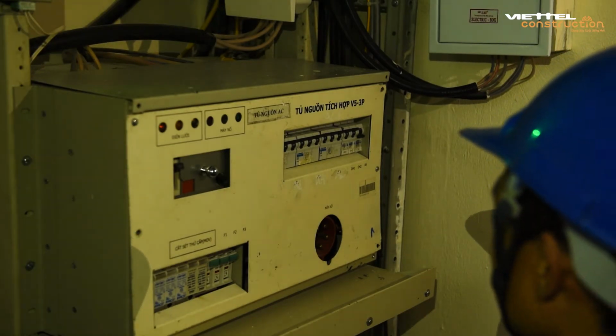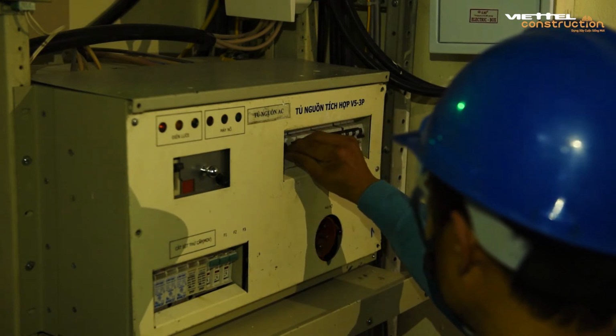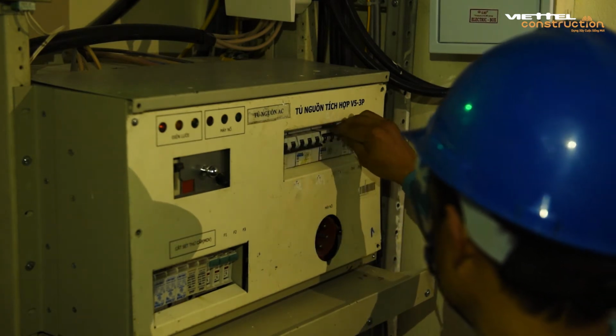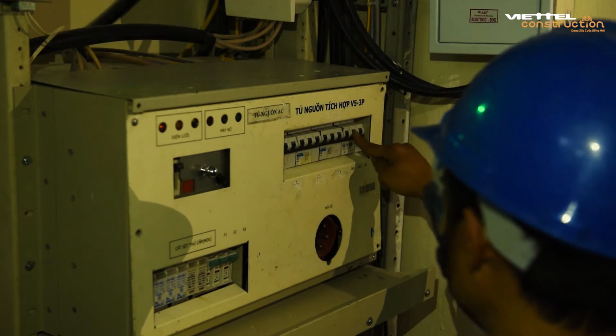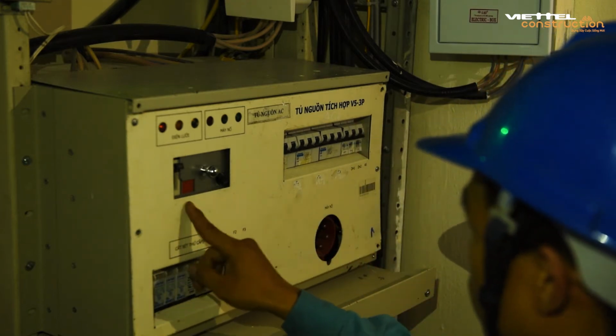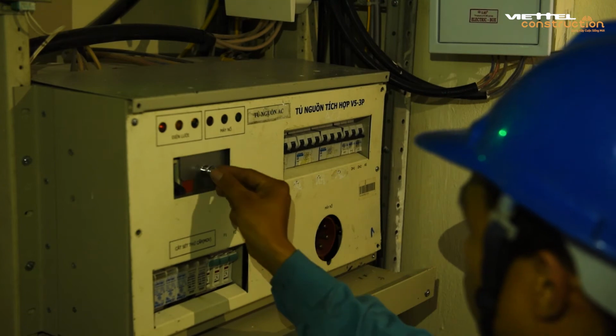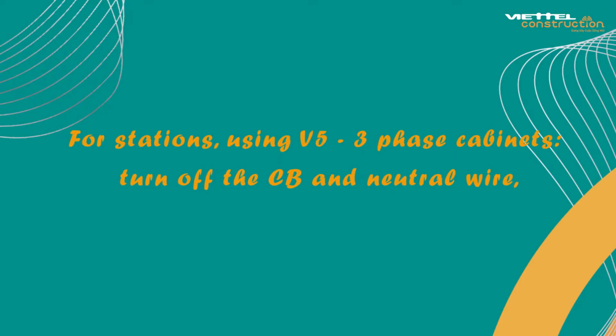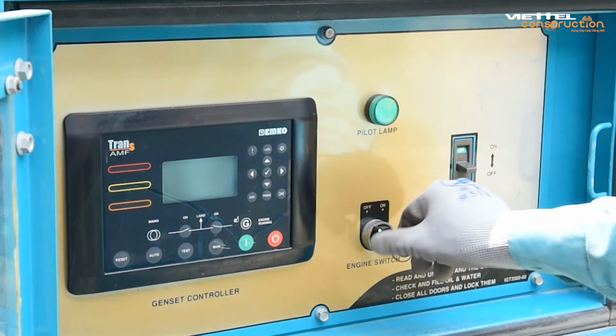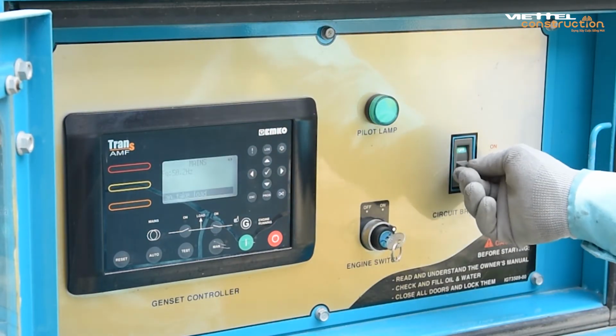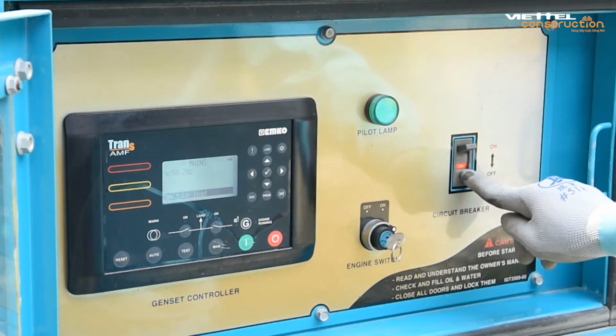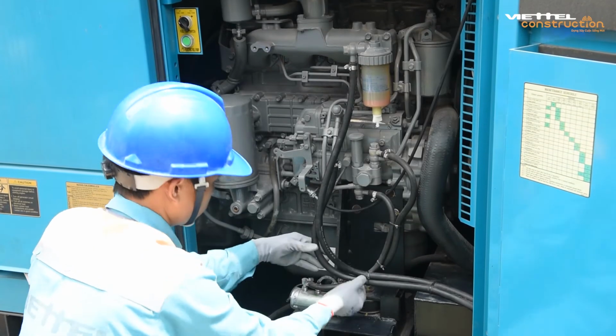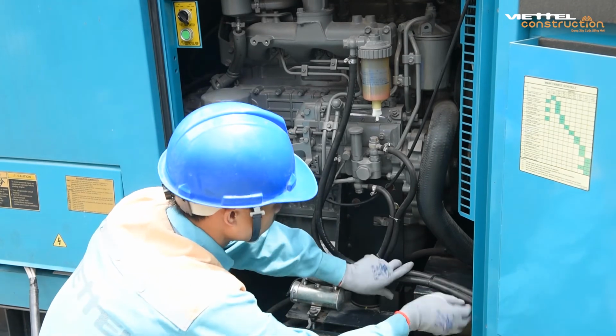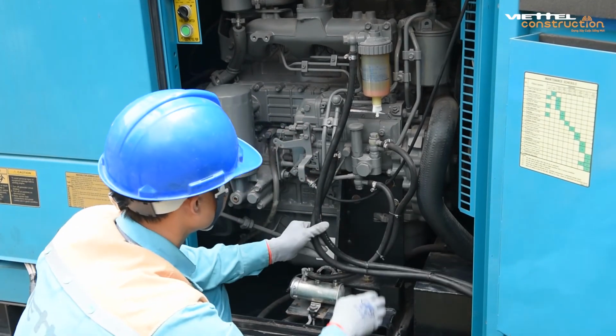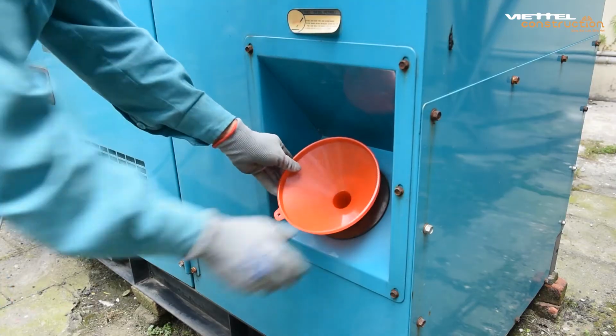Before starting the generator, it is necessary to disconnect the total circuit breaker of the electric network connected to the device and the circuit breakers (CB) used to distribute electricity for telecommunications such as lighting, other equipment. For stations using V5 3-phase cabinets, turn off the CB and neutral wire, turn on the switches to work mode. Check the fuel pipe system, make sure there is no broken or leaking. Fill the fuel up.